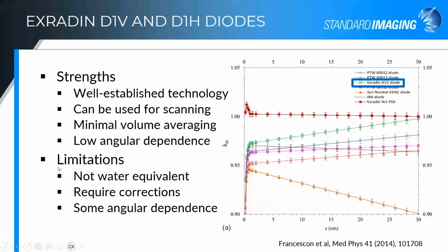Strengths of these diodes, as I mentioned, diodes are well-established technology. We have been using them for years. You can use them for scanning very easily. That 1 millimeter active area gives you minimal volume averaging. Our diodes have a low angular dependence, so you don't have to worry about the angle when you're scanning off to one side. Although with small fields, that's of course less of a concern than a larger field.